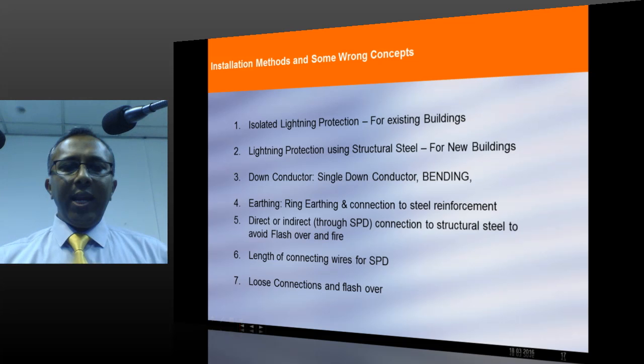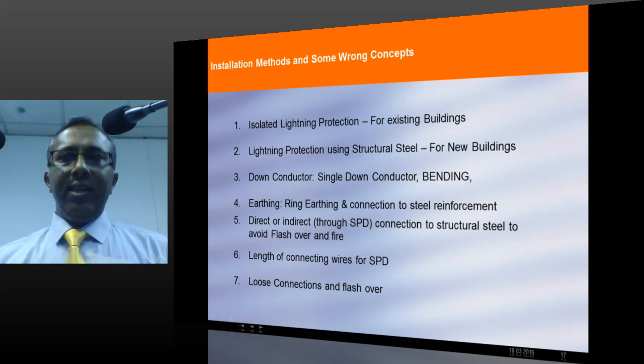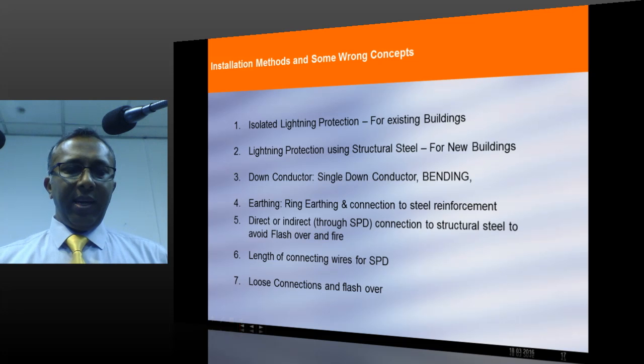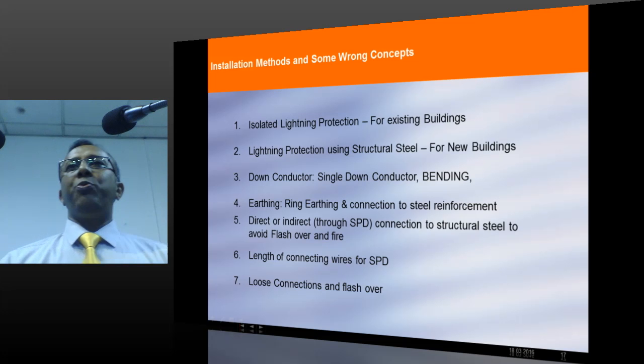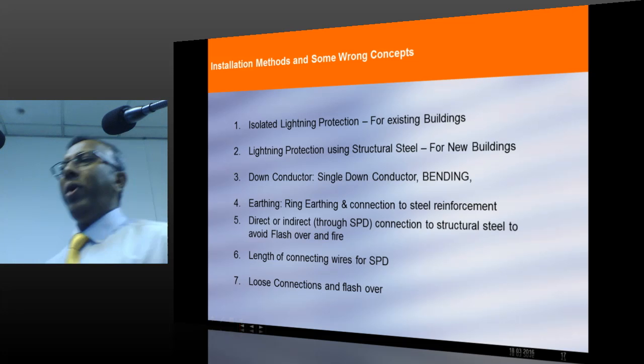So, direct or indirect connection to structural steel to avoid flashover and fire. This is also explained later. Length of connecting wires of SPD. You know, nowadays, for the last 5-6 years or maybe the last 10 years, knowledge of SPD, surge protection devices, has become common. Engineers know what an SPD is and what it does.